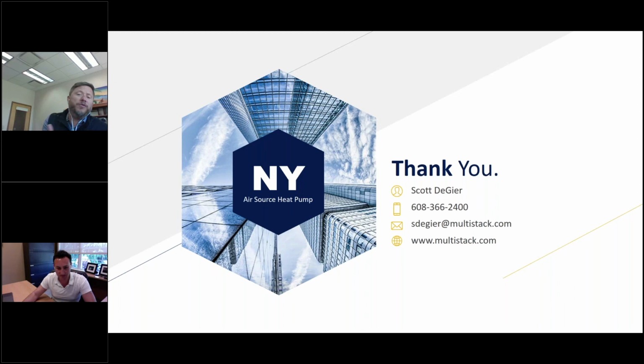And by the way, just so you know, we talk about some of those installations that are, let's say, installed inside the building. Not only can they be used to do the cooling and the heating, right? So if we're going to be making the chilled water and hot water used directly at the terminal devices, they can do that. We've also seen them used in lieu of, let's say, a boiler and a tower if you're going to have a heat pump building, right? So if you're going to have heat pumps serving a residential building, as an instance, with heat pumps in every one of them, or it's a hotel, we have seen an air source heat pump utilized as a heat source and heat sink in lieu of, like I said, a tower and a boiler, or a geothermal loop, or in combination with those things.